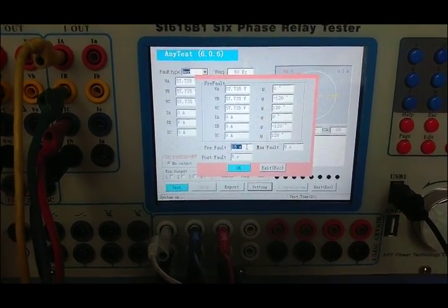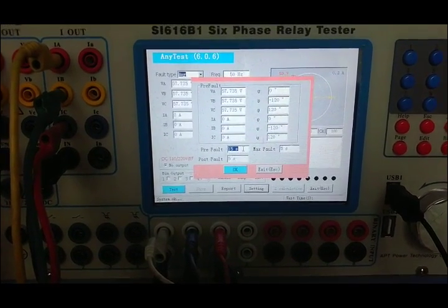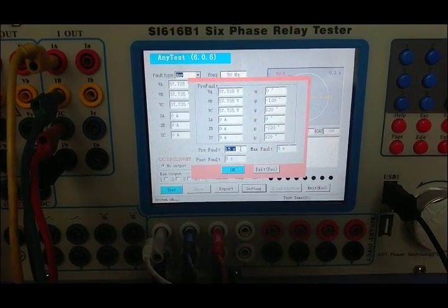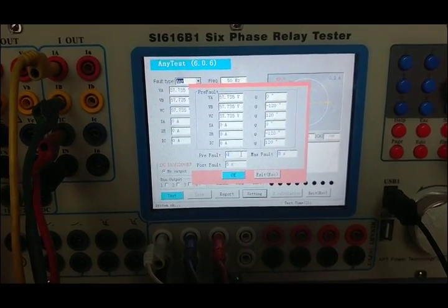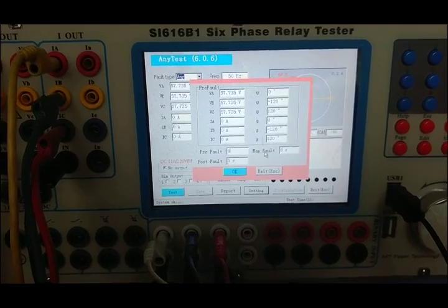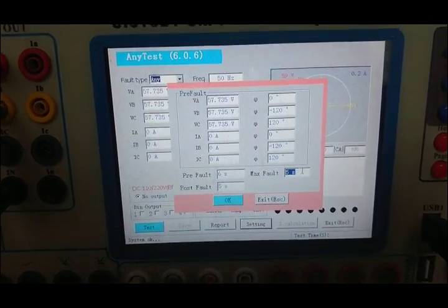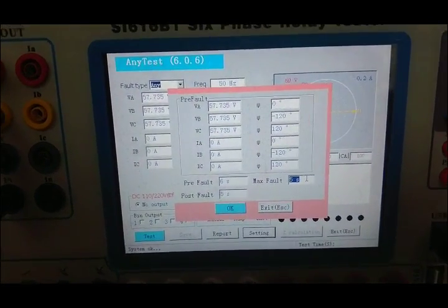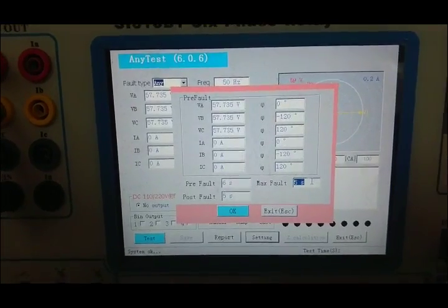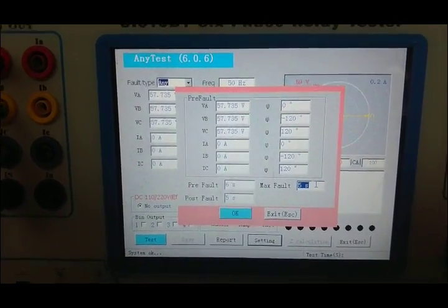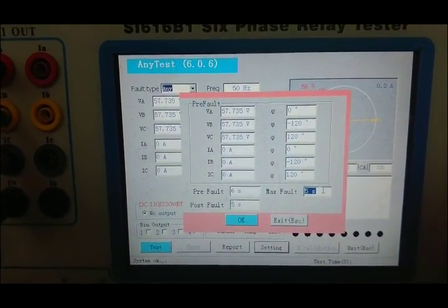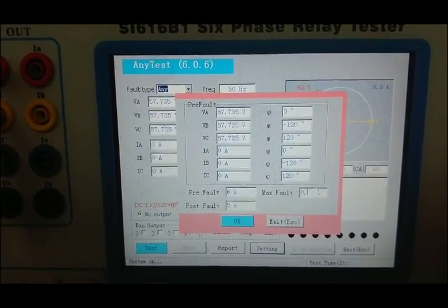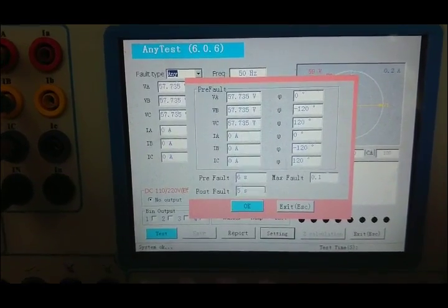Pre-fault time is usually 15 seconds; our pre-fault time is 6 seconds. The setting time of the first zone is 0 seconds, so we set it to 0.1 seconds.